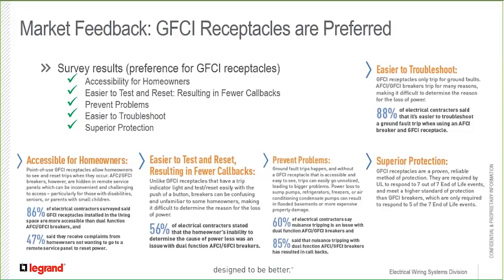Another reason why GFCI receptacles are preferred, they are easier to troubleshoot. GFCI receptacles only trip for ground faults. AFCI, GFCI circuit breakers trip for many reasons. 88% of electrical contractors surveyed said that it's easier to troubleshoot a ground fault trip when using an AFCI breaker and a GFCI receptacle. We've had numerous people tell us that consumers have removed these devices, the AFCI, GFCI circuit breakers, because they're unable to determine the cause of nuisance tripping and are unwilling to pay to have it investigated. So we've had people tell us that they've removed these devices and replaced them with standard circuit breakers, which can potentially leave them in a dangerous situation where liability could be had all the way around.